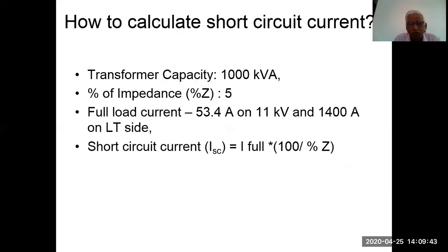Now, how to calculate short circuit current? Take an example of a transformer capacity of 1000 kVA. Percentage impedance, percentage Z, is 5%, given on the transformer. Full load current of the 1000 kVA transformer at 11 kV is 53.4 amperes. At the LT side, it is 433 volts, so it is around 1400 amperes. Short circuit current will be full load current, in this case 1400 amperes, that is 1.4 kiloamperes, multiplied by 100 by Z.